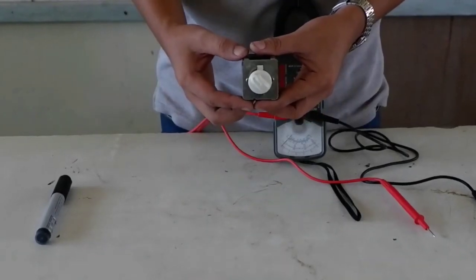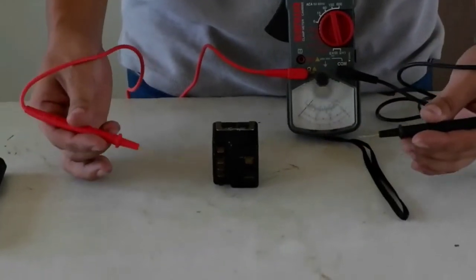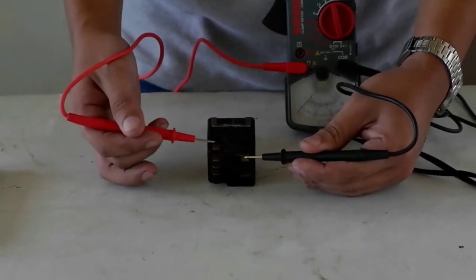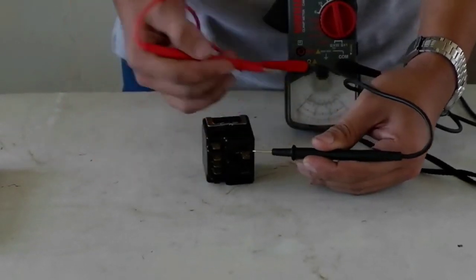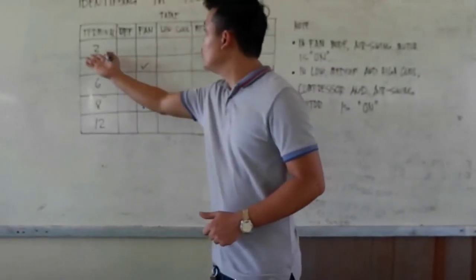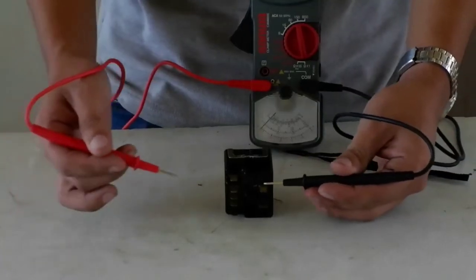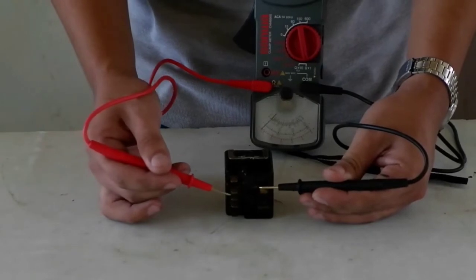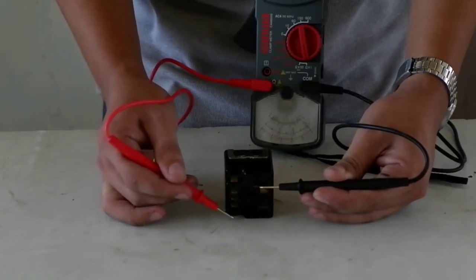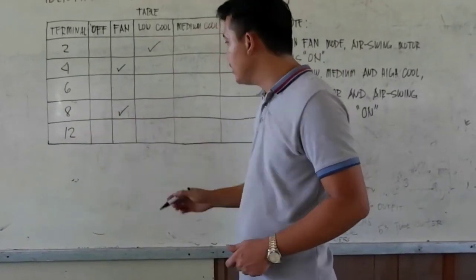Now we are going to rotate the knob into low cool. Again, we are going to test each terminal for deflection. Terminal 2 has a deflection — we record it. Terminal 4 has no deflection. Terminal 6, no deflection. Terminal 8 has a deflection. Terminal 12 also has a deflection. So in low cool, terminals 2, 8, and 12 have deflection.